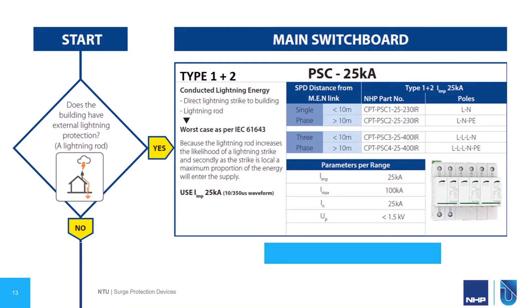The PSC 25 kA has an impulse current of 25 kA, a maximum current of 100 kA, a nominal current of 25 kA, and a voltage protection of less than 1.5 kV. Part numbers can be selected from the chart depending on whether it's a single-phase or three-phase installation, and whether the installation is less than or greater than 10 meters from the MEN link.